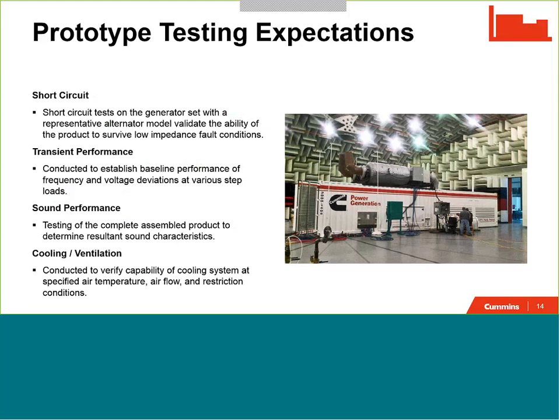Moving into some additional prototype testing expectations, short circuit capability is one that is clearly called out by NFPA 110. However, again, this is one where you should ask some additional questions to understand the true performance capability of the generator set manufacturer as it relates to the short circuit testing that's been conducted on that product, in addition to considering the inherent short circuit protection that may be included in the generator set manufacturer's controls package. Transient performance is another key piece of prototype testing, as this really helps to establish a baseline of performance for the product once a unique configuration is assembled for your particular project and for when it's installed on site.